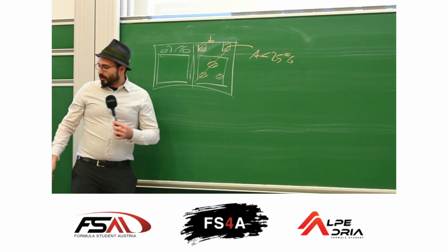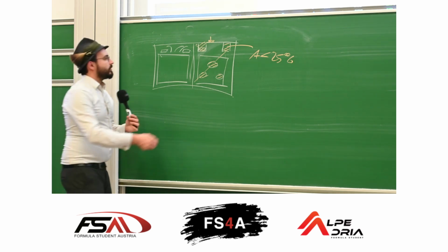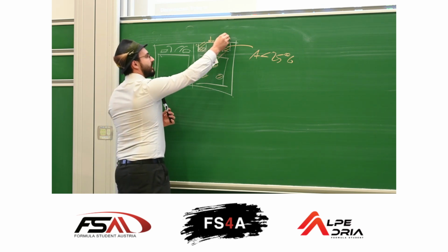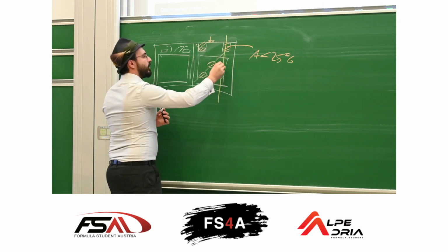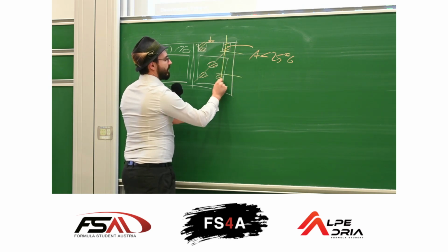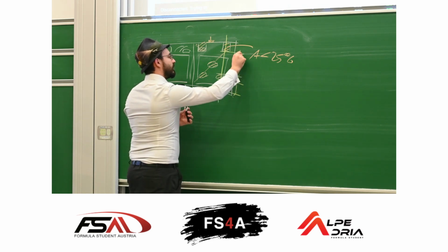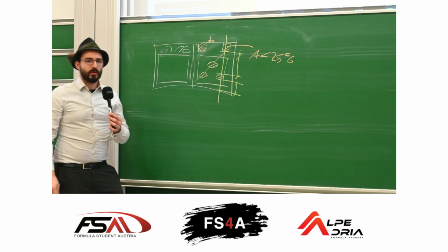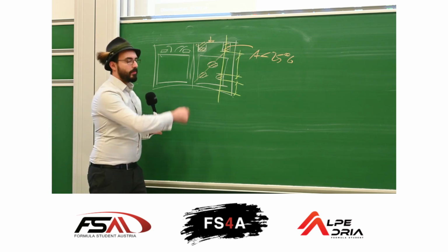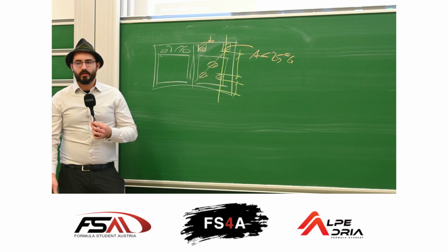And now with regards to the mechanical and how to implement it in your SES, you have to take the section which is the weakest point, which is right here, and the remaining panel height, which is this value plus this value. This is the panel height which remains with regards to your structural equivalency, and this is the panel height that you put into your accumulator SES for the structural documentation.